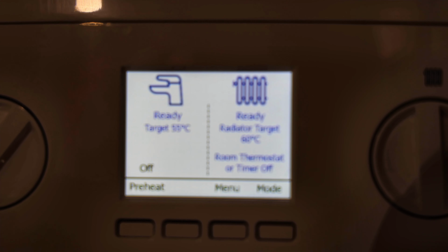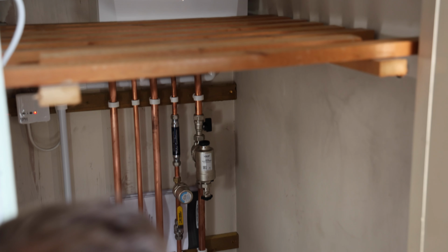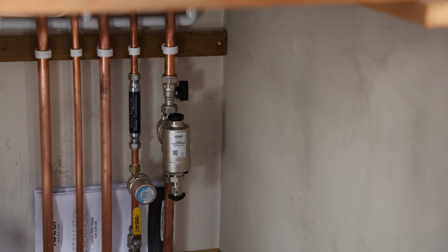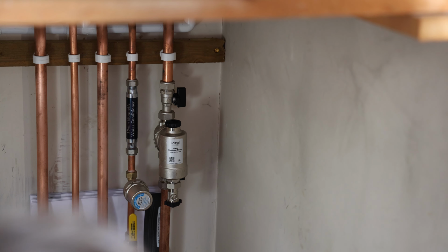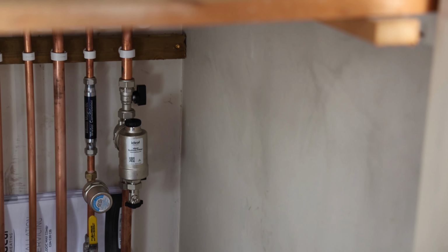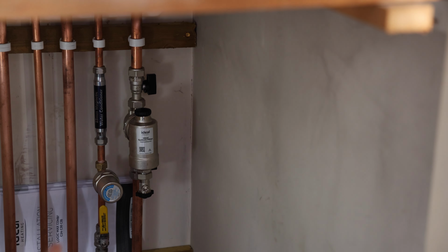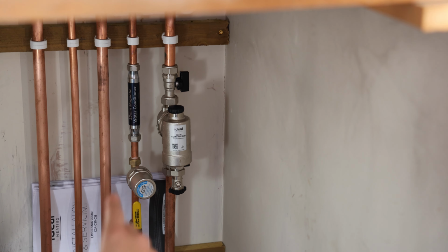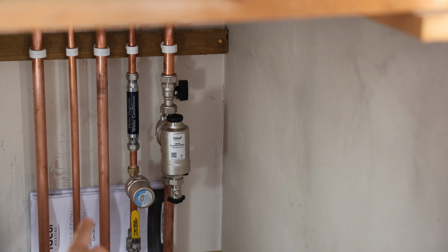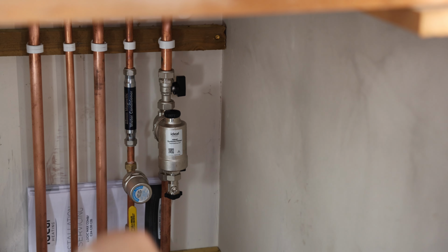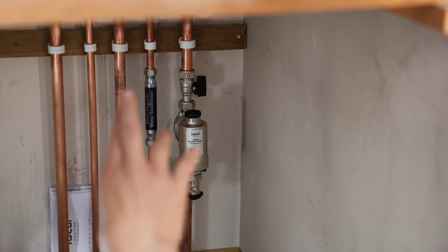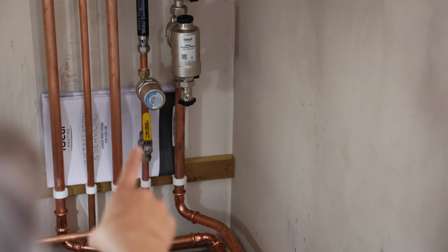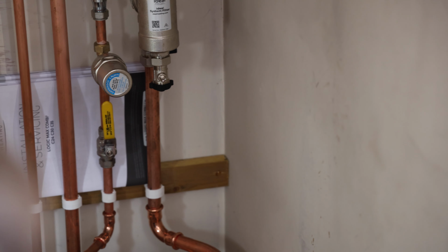So that basically collects any dirt and rubbish out of the system. When it comes to the boiler being serviced, that filter is also serviced and taken out. And then to the left of it, you can see a water conditioner. That's on the cold main side. The water conditioner basically protects the boiler from limescale. And then if you go one down, you've got a silver circular dome. That's called a shock arrestor.